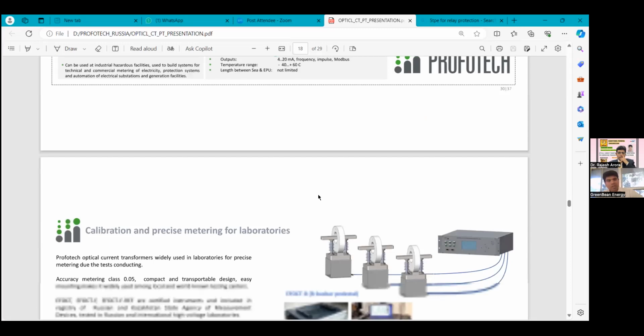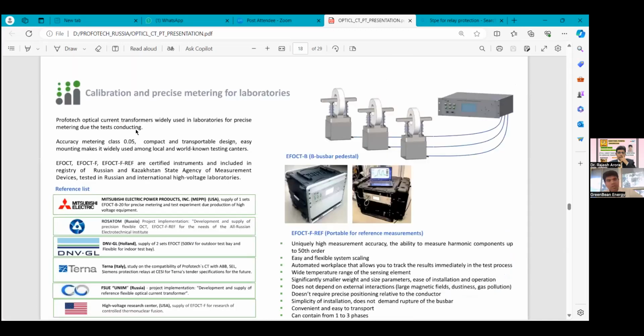This device is used for calibration and precise metering for laboratories. The Profotech optical current transformers are widely used in laboratories for precise metering due to the test conducting. Accuracy metering class 0.05, compact and transportable design, and easy mounting make it widely used amongst local and world-known testing centers. EFOCT, EFOCTF, EFOCTF reference are certified instruments and included in the registry of the Russian and Kazakhstan State Agency of Measurement devices, tested in Russian and international high voltage laboratories.